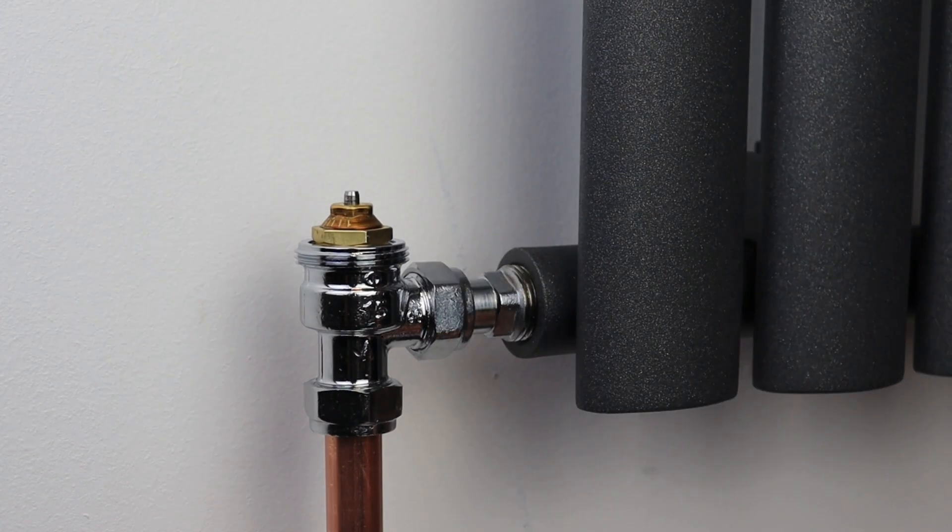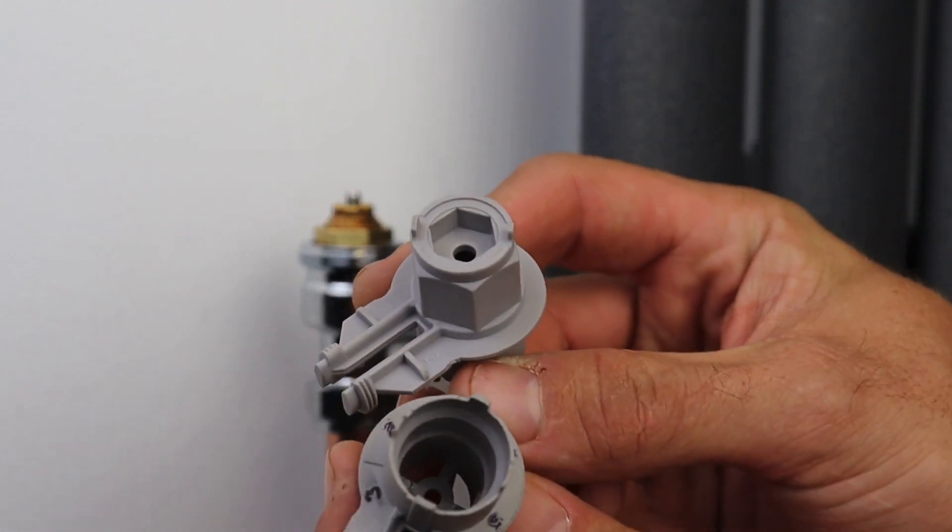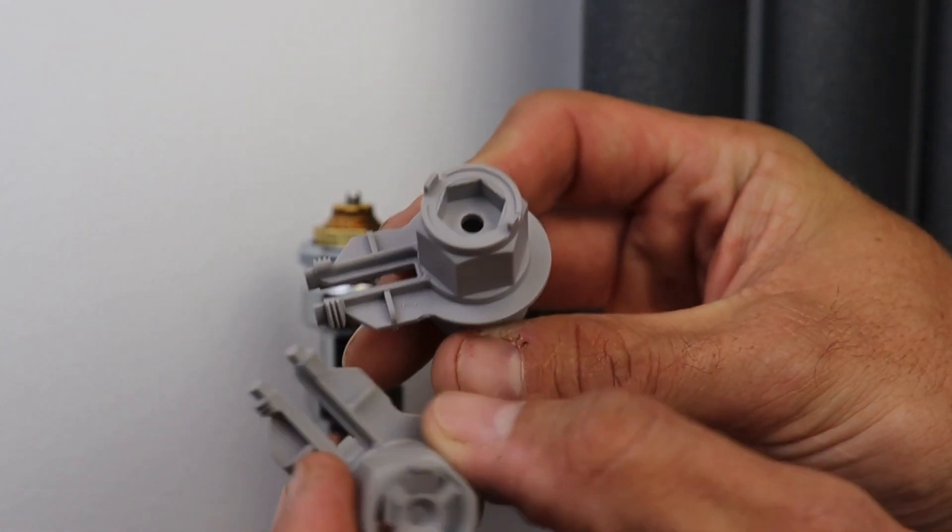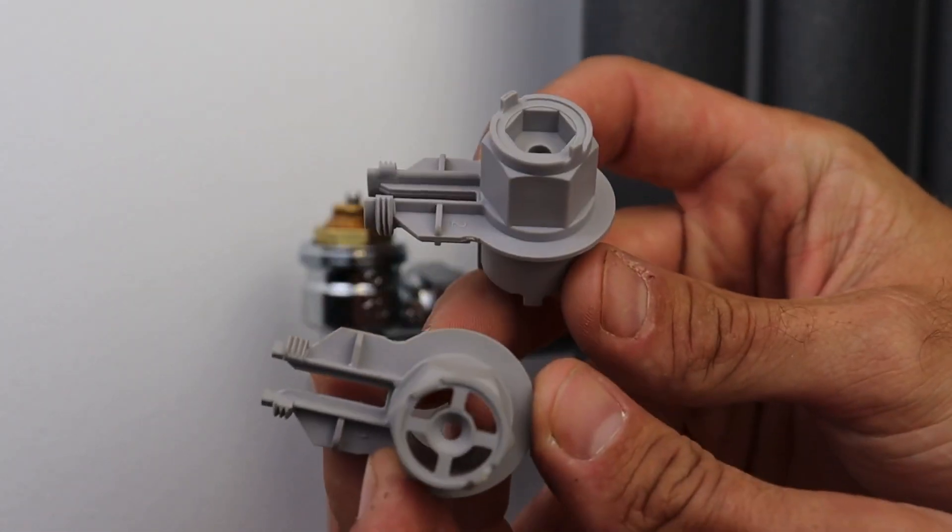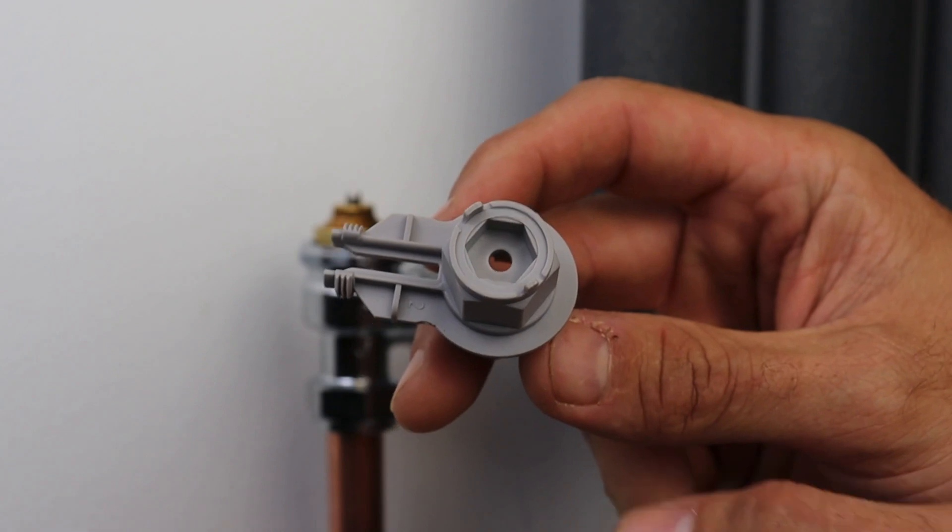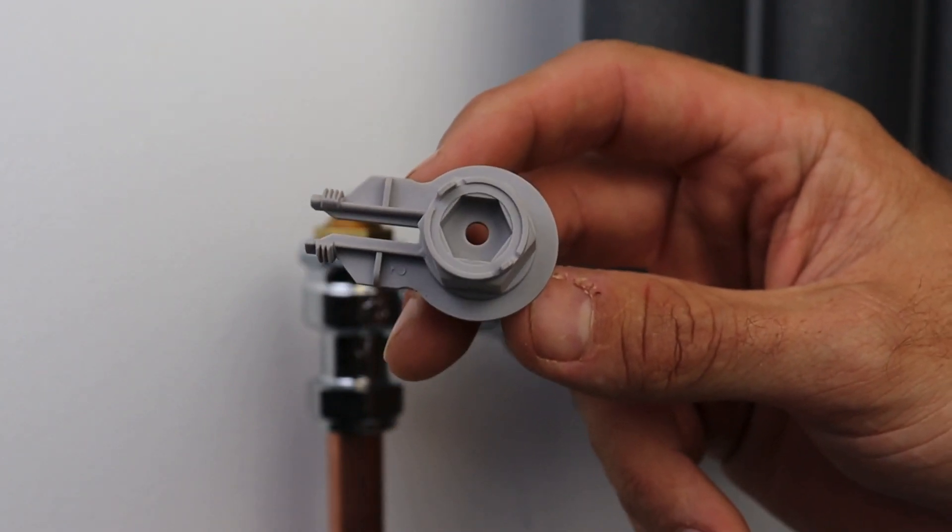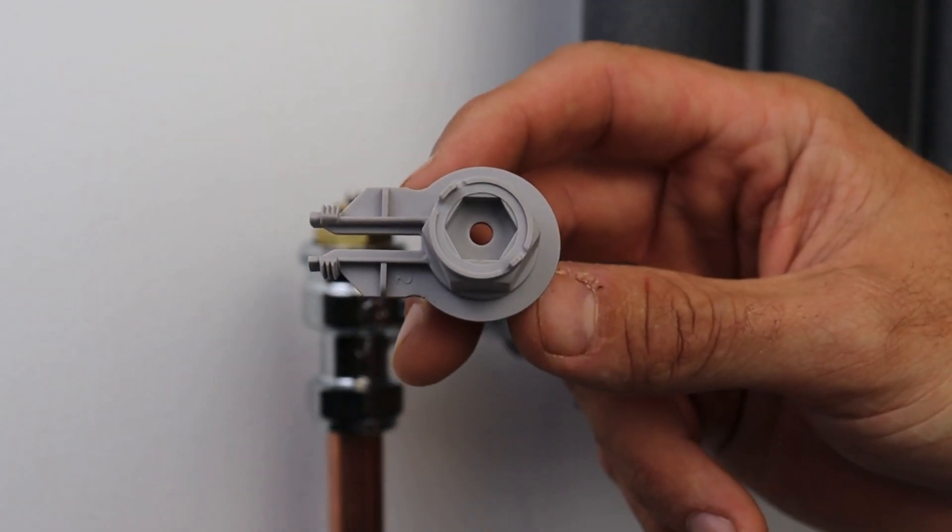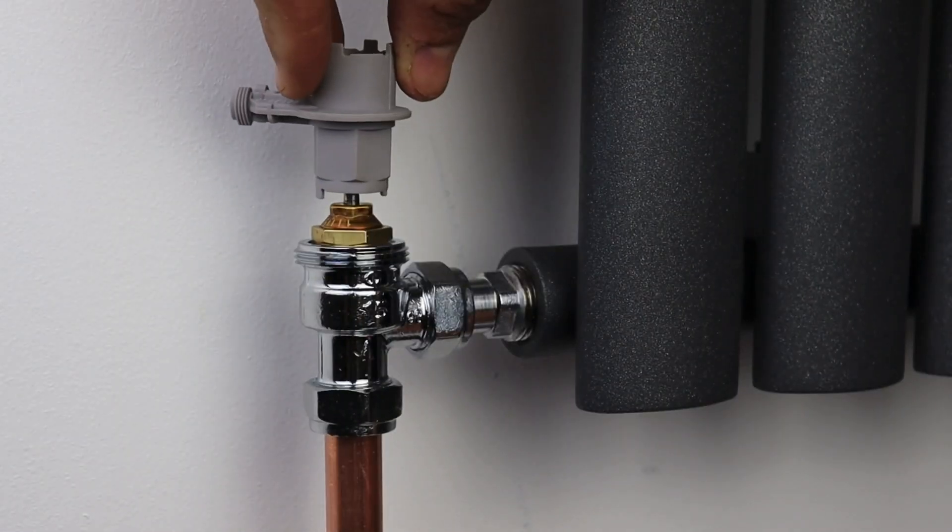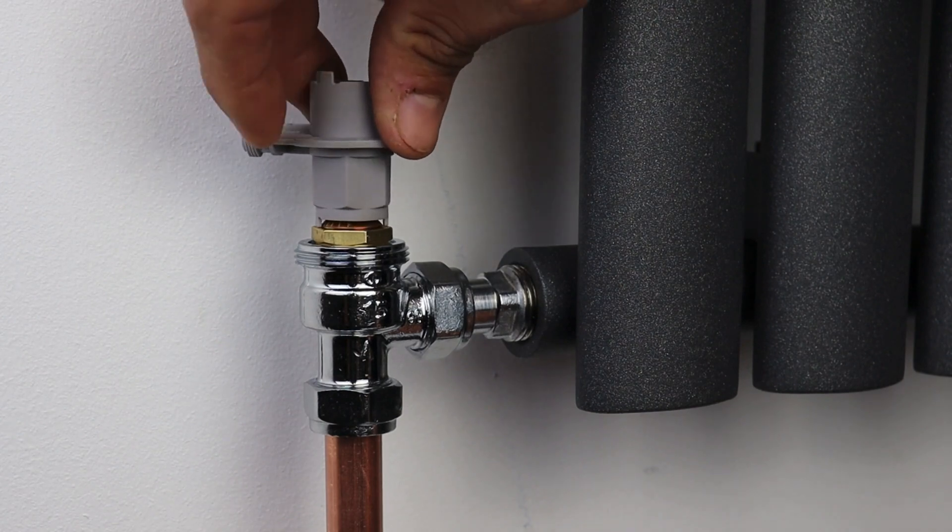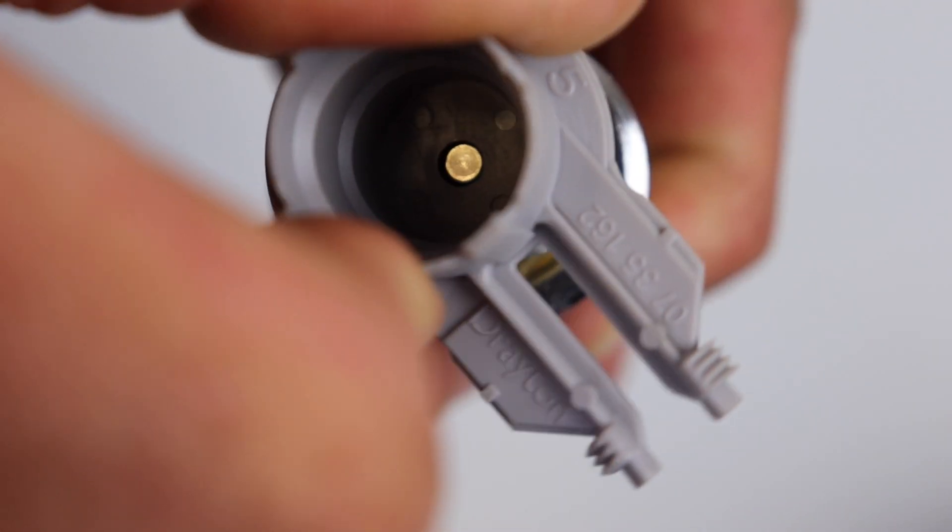With that installed we are now ready to commission the system and we do that using again the Drayton balancing key. Now you'll see there's two differences between these. This is the old one but with the advent of the auto balancing valve we've now included the hex on one end so that now fits onto the top of the valve to allow you to turn it to the appropriate setting.